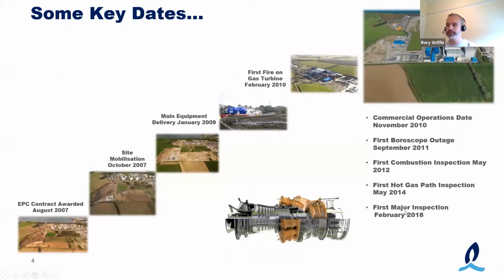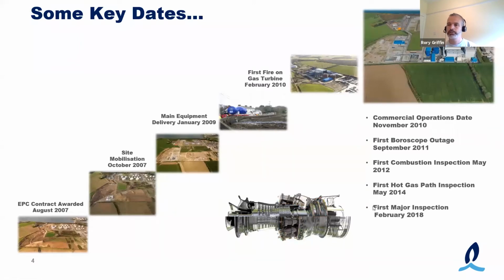The last of the milestones on this slide then is the first major inspection in February 2018. This covered, again, the combustion cans would have been changed out in the machine, the gas turbine blades, and the first major inspection on the steam turbine. So the covers were lifted for the first time. An assessment was then taken on the rotor of the steam turbine as well as the bearings. And we did a more detailed inspection on the generator as well.